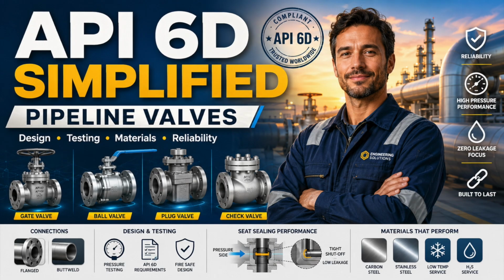Plug valves bring their own logic. They can be robust and effective, but they may involve higher operating torque, lubrication, pressure balancing, and maintenance dependence. If the valve depends on sealant, can the correct sealant be used in the process fluid? Can it survive the operating temperature? Can maintenance personnel reach the injection point? Is the valve buried? Is the extension practical? A valve requiring maintenance access but installed without access is not a maintenance problem. It is a design failure.